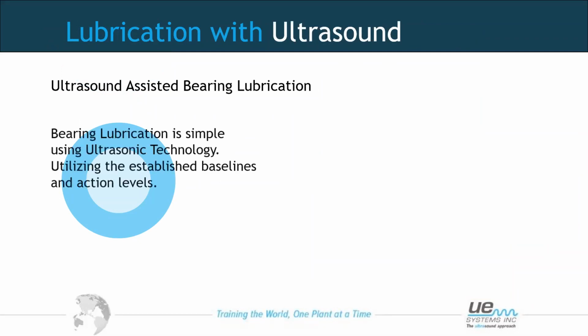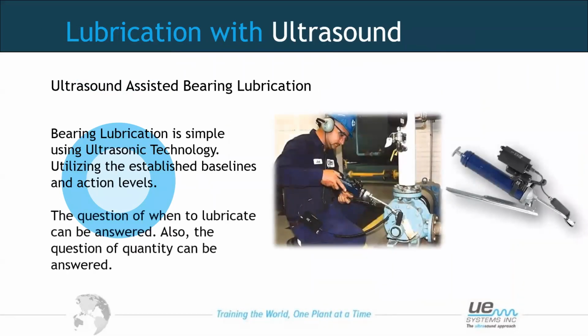So when it comes to lubrication with ultrasound, again, we're looking at the friction levels. And using ultrasound, we can listen as we apply the grease. It can help us understand when to lubricate as well, because we can set baselines and alarm levels that notify us when there is a rise, and it helps us with actually applying the grease.